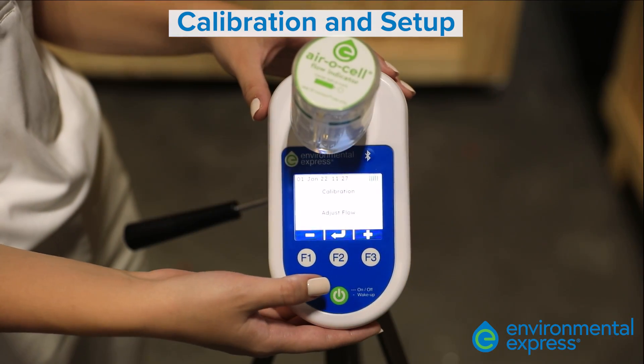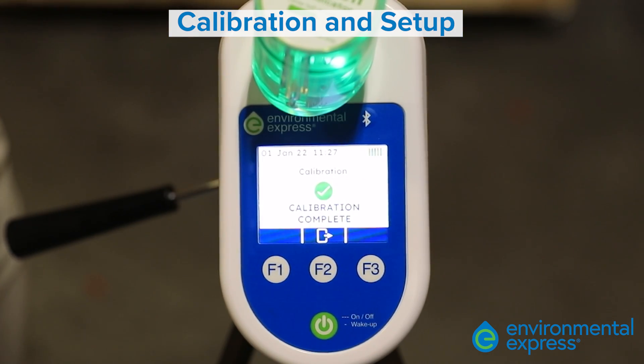When satisfied with the position, select the middle arrow button. The screen will then display calibration complete. Once calibrated to 15 L per minute — the flow rate required for mold collection — we are ready to begin sampling.